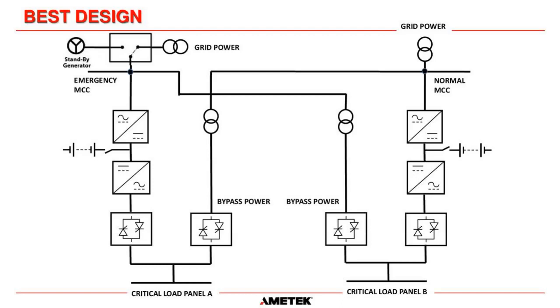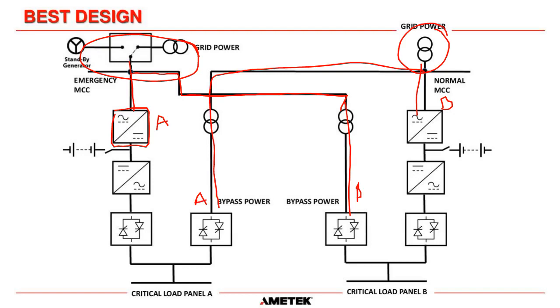So we basically still have our emergency power in the top left-hand corner here through the automatic transfer switch. And the emergency MCC feeds the AC input into the rectifier of UPS A. And the emergency feed will also feed the bypass of UPS B. Okay. And then on the other side, you will have your normal MCC, and it will feed the AC input to the rectifier of UPS B, and then it will feed the bypass supply of UPS A.